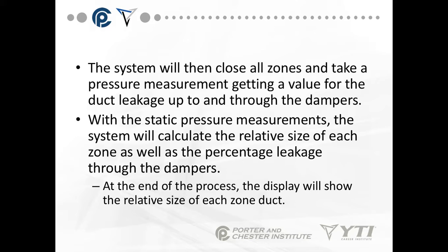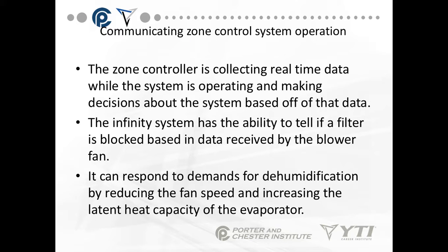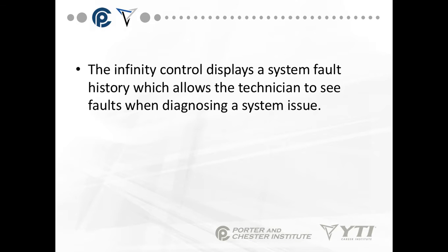At the end of the process, the display shows the relative size of each zone — essentially confirming the ductwork is good. The zone controller collects real-time data while the system is operating, making decisions about how to run the system off that data. The Infinity system can also detect a blocked filter based on data from the blower fan, respond to demands for dehumidification by reducing fan speed and increasing the latent heat capacity of the evaporator, and displays a system fault history, allowing the technician to see faults when diagnosing a system issue.